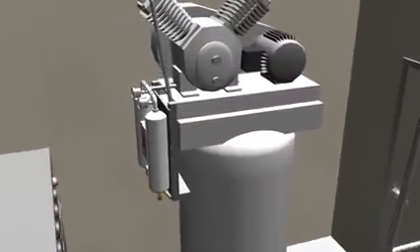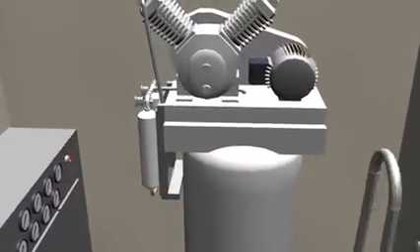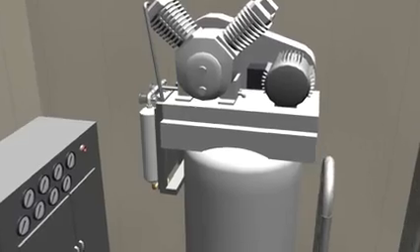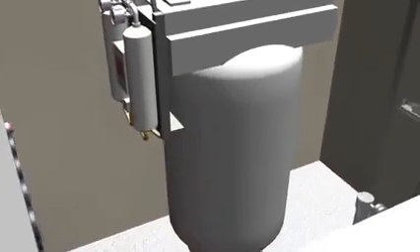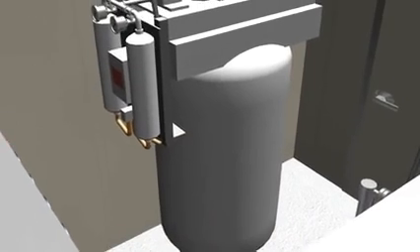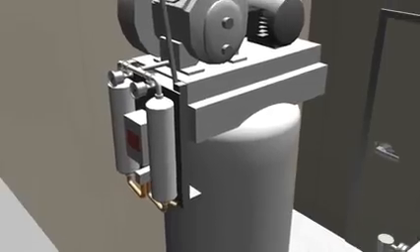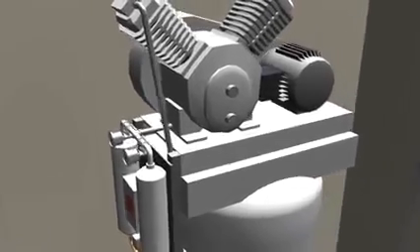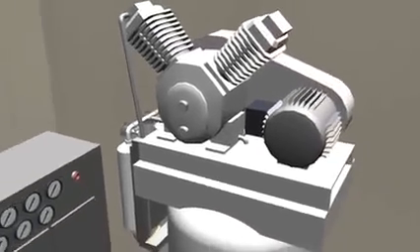The instrument air compressor and storage tank provides a backup supply for pneumatic control devices. Normal air supply for pneumatics is supplied by the combustion turbine compressor discharge when the unit is in operation. The auxiliary air compressor supplies instrument air when the combustion turbine is not in operation.